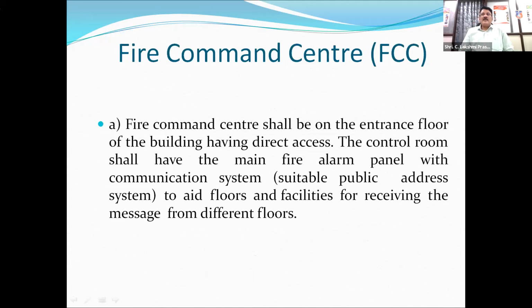Then the NBC also prescribes a fire command center, which should be there in all high-rise buildings. It should be like a control room which should have all the building services monitoring systems, and there should be an exclusive person available to take care of the fire command center. It should have all the panels of alarms, communication, sprinklers, fire pumps, for their functioning or use. The entire thing should be available in the fire command center. This should be located at the ground level of the building. It should not be elsewhere, it should not be in the basements. It has to be provided on the ground floor only.